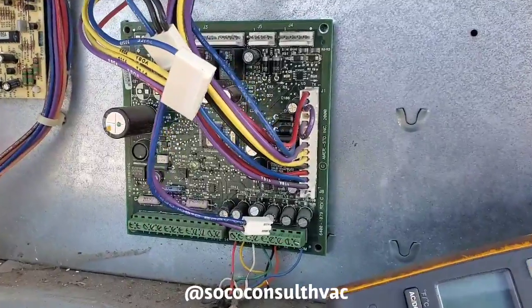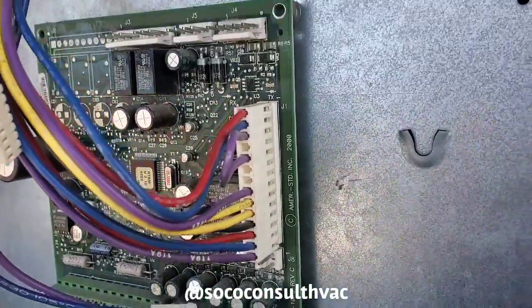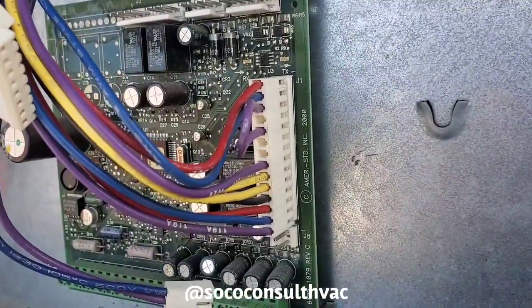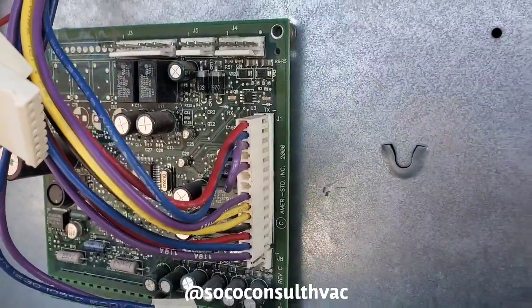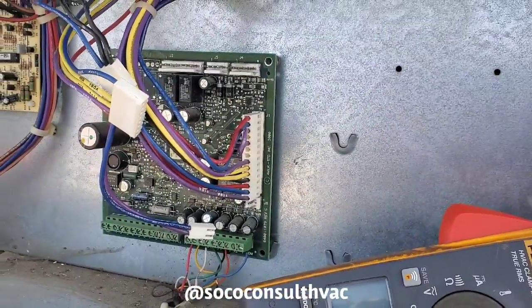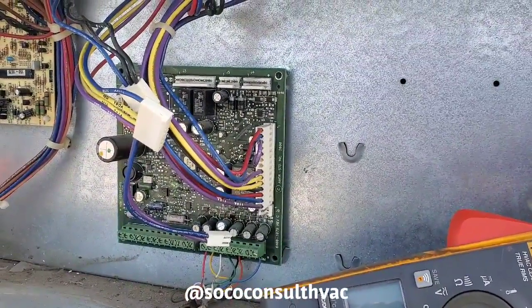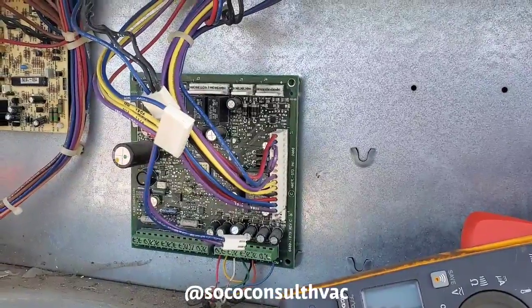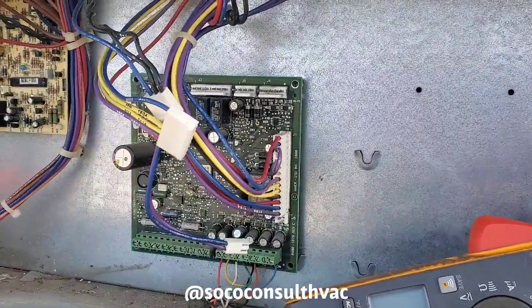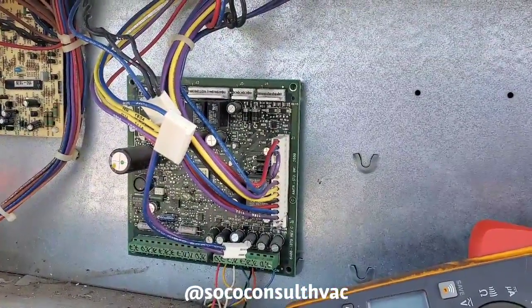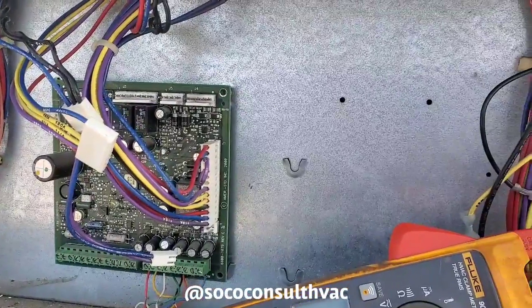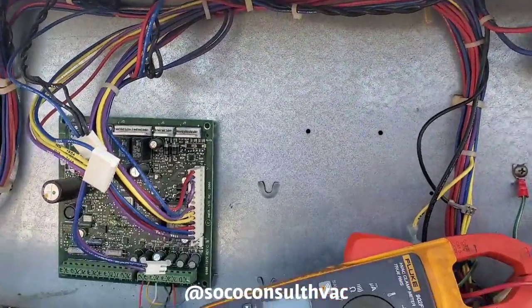Now it's time to determine which one of those wires is going to a component that's actually shorted. This is called the isolation method, and it's pretty much the best way of determining a low voltage short. That's usually very difficult for technicians to find. Essentially, you're removing things from the equation until you figure out what is and what is not blowing that fuse.